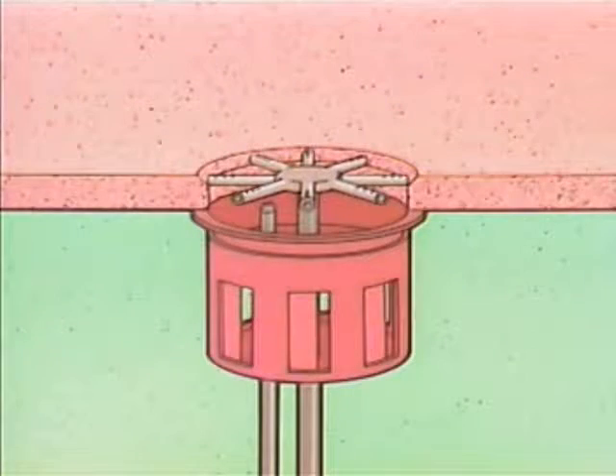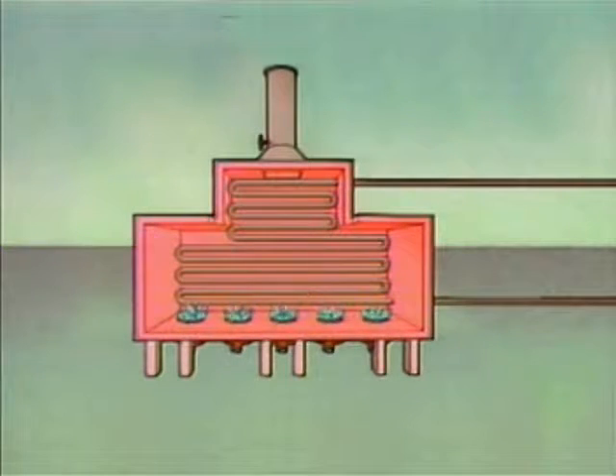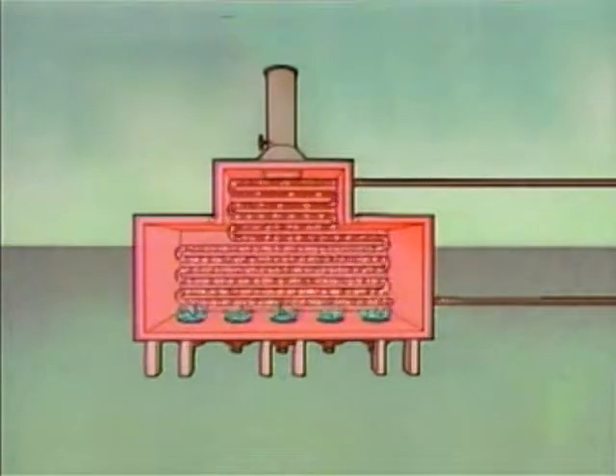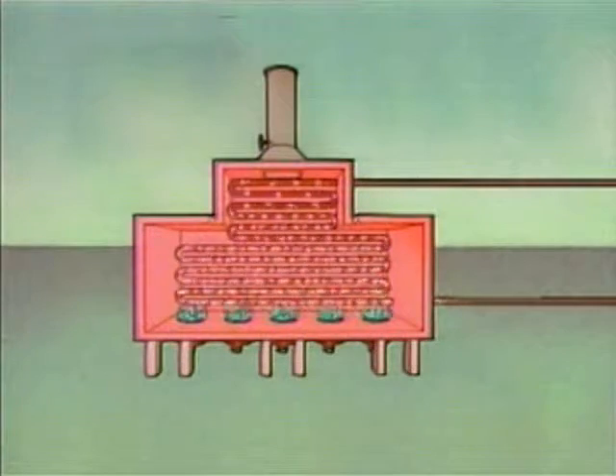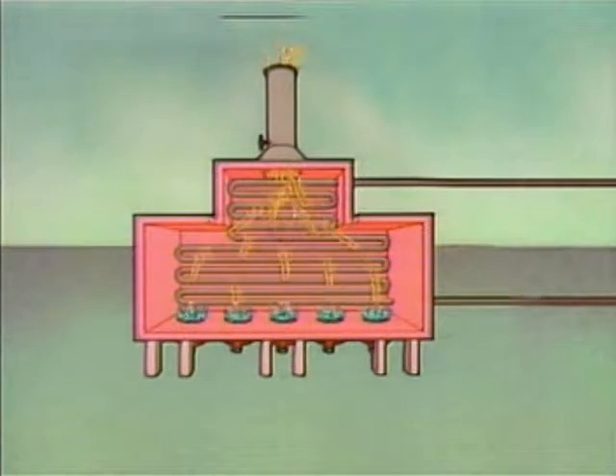All of the parts and systems associated with a furnace are used to accomplish one basic task: heating a process fluid. We can break furnace operation down into three basic actions. In the first action, air and fuel are introduced into the furnace and mixed together by the burners; the mixture is ignited, and as the fuel burns, a chemical reaction occurs and heat is produced. In the second action, heat released by the chemical reaction is transferred to the process fluid, which flows through the tubes inside the furnace and receives heat by conduction, convection, and radiation. In the third action, the combustion gases produced by burning fuel rise through the stack and are exhausted to the atmosphere.